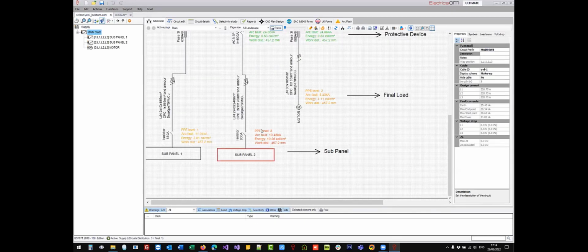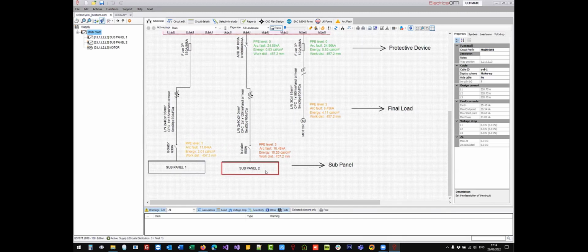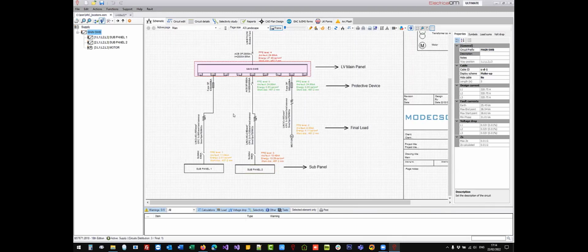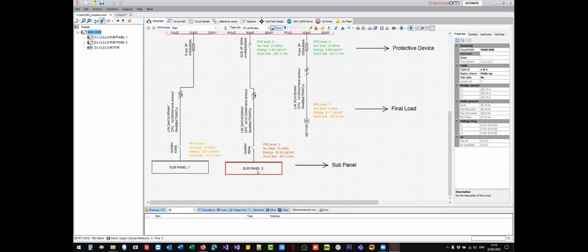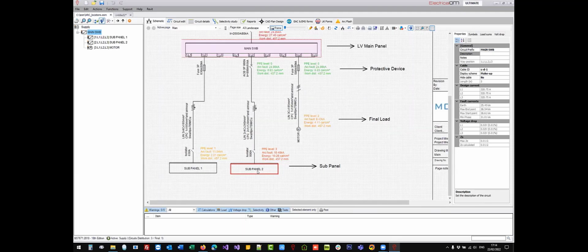And if I go back to the locations diagram I created here, I have an example where this panel is protected by specialized equipment by Eaton that has a specific component called ARMS.